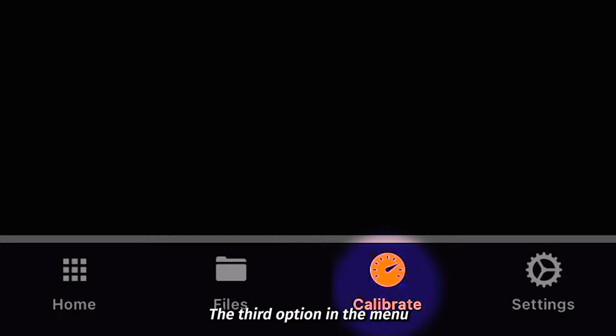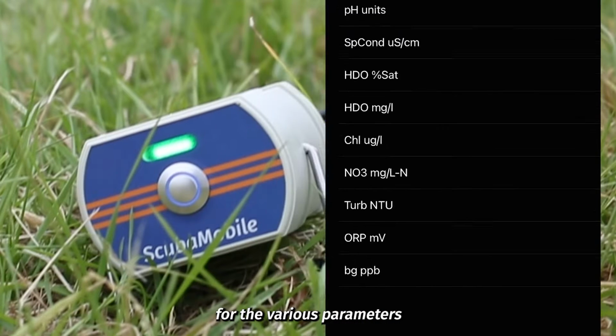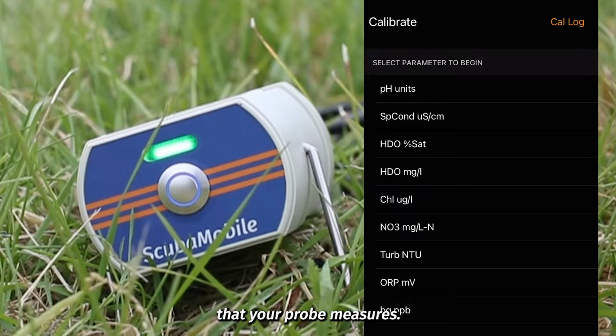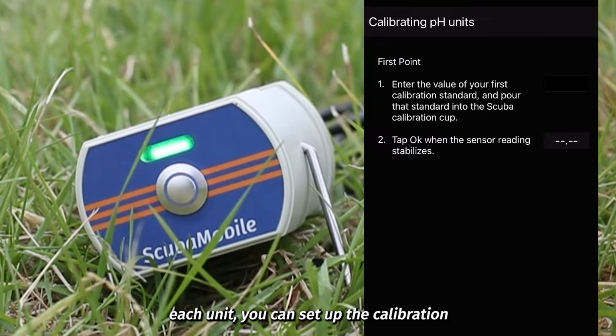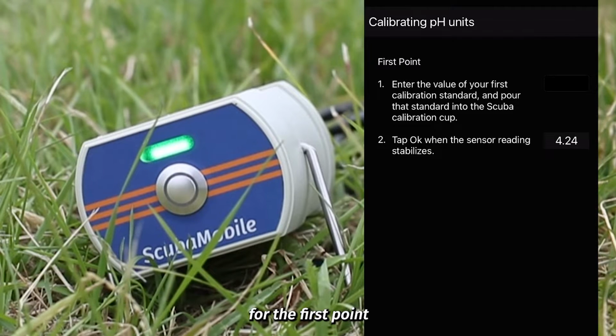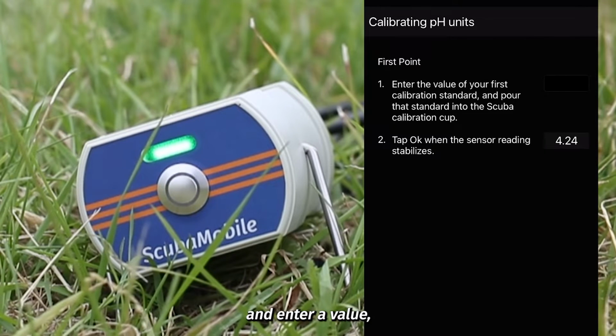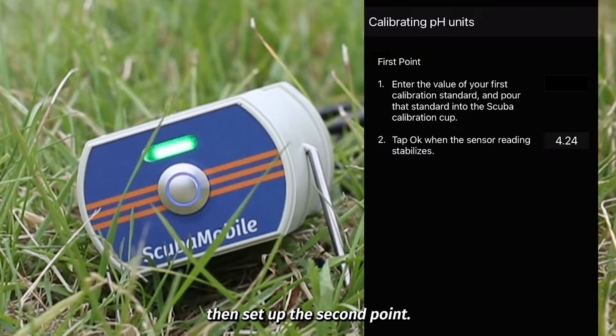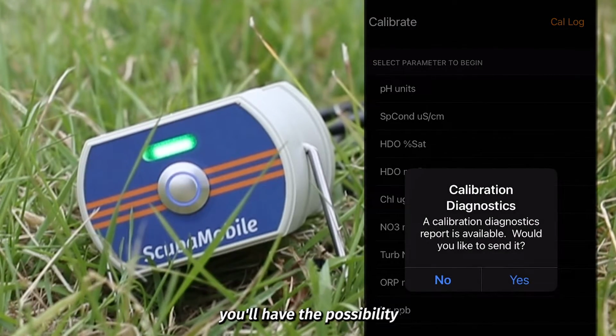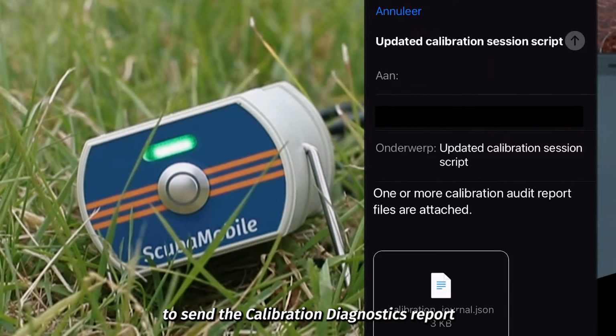The third option in the menu is to calibrate your probe for the various parameters that your probe measures. For instance, if you select pH unit, you can set up the calibration for the first point and enter a value, then set up the second point. When finished, you'll have the possibility to send the calibration diagnostics report to any email address.